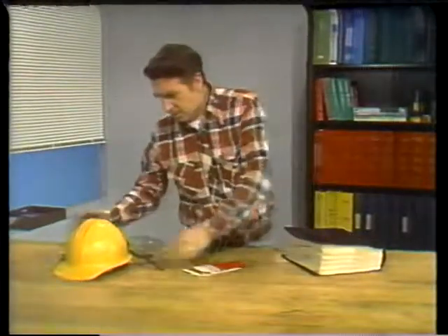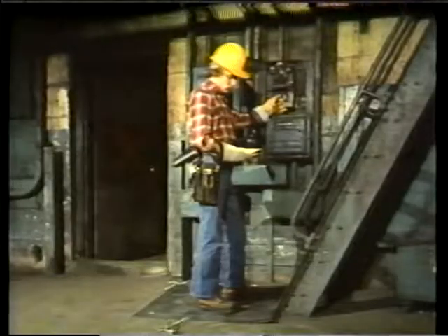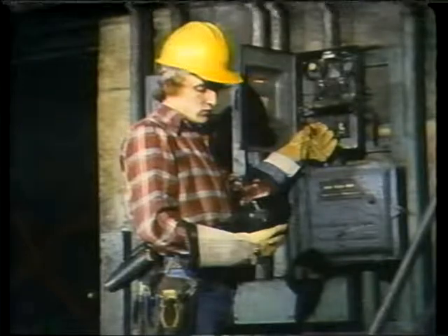Of course, you want to make sure a proper tag out is performed, and you always want to wear the regular safety equipment. You want to wear a hard hat and gloves and glasses. Now, if you're going to be performing electrical maintenance, there are some other very important precautions. They include using rubber gloves, rubber matting, and insulated tools. Also, don't wear watches or rings or belt buckles. These are all metal and they conduct electricity. Wearing them during electrical maintenance could result in severe shocks or burns.